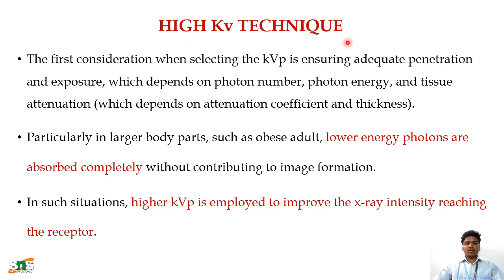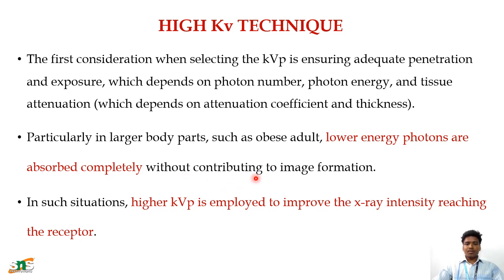What is High KV Technique? In selecting the KVP, ensuring adequate penetration and exposure depends on photon number, photon energy, and tissue attenuation, which depends on the attenuation coefficient and thickness of the object. Particularly in large body parts like obese adults, lower energy photons are absorbed completely within a few centimeters of tissue without contributing to image formation. To improve X-ray intensity, which improves the penetration of photons and contributes to image formation, that is why we use the High KV technique.